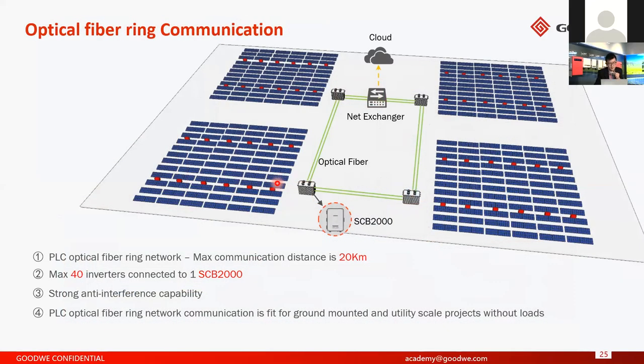And here is optical fiber communication. If you have a big plant, for example 10 megawatt or 20 megawatt, the distance between the transformer stations is very long, already more than 1,000 meters. So you can't use RS485 cable to connect the transformer stations. In this case, we have the SCB 2000 with optical fiber. You can connect each transformer station with the optical fiber, and the maximum distance can reach up to 20 kilometers.